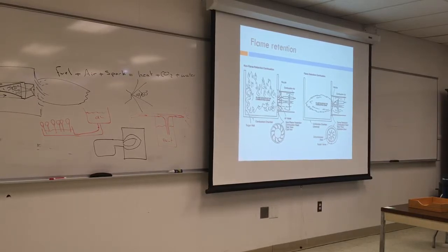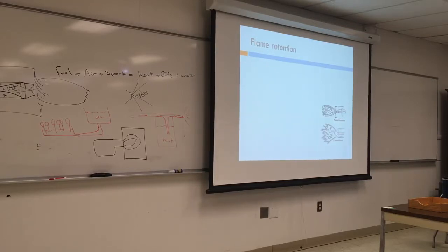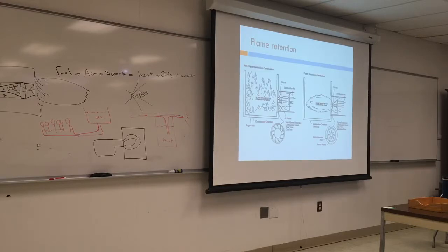Question about that? We did take a whole burner apart and put it together again, so we know what it looks like. Yeah, they'll ask you about the angle, what is the purpose of the angle, what is the purpose of the turbulator. So 60 degrees? No, it always depends on the manufacturer specification. So you always stick with whatever is printed on the burner. It should say on it what is the spray angle and what is the pressure. How do you check the angle? The angle should be printed on the nozzle. You see the nozzle that I passed around? Look at it. It will show the angle on it.